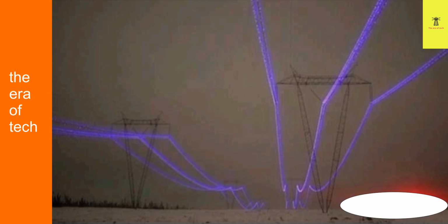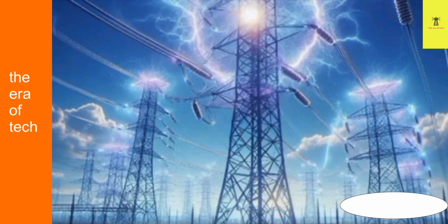The corona effect is the ionization of the air surrounding a conductor when the electric field intensity around it exceeds the critical disruptive voltage. In simple terms, when the voltage on a transmission line becomes high enough, the air around the conductor breaks down and starts to conduct electricity partially, creating a glowing discharge.